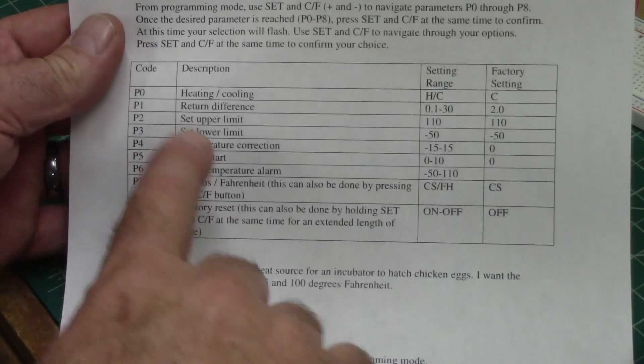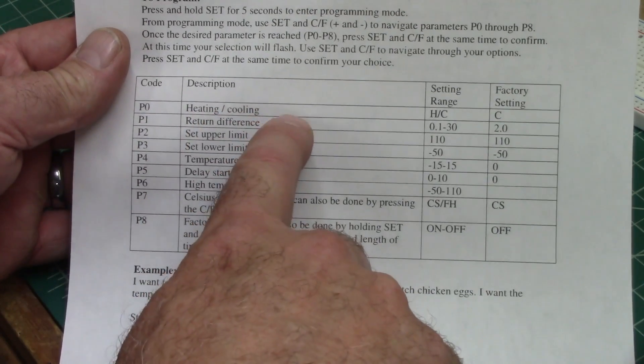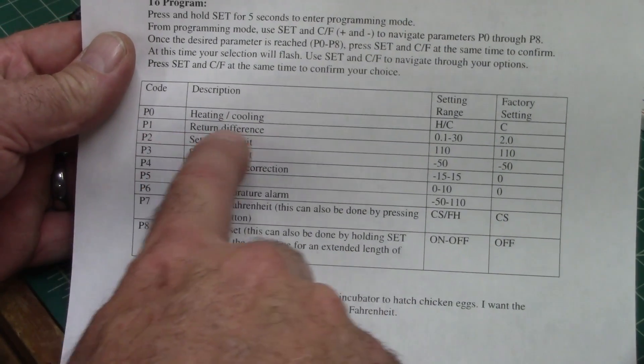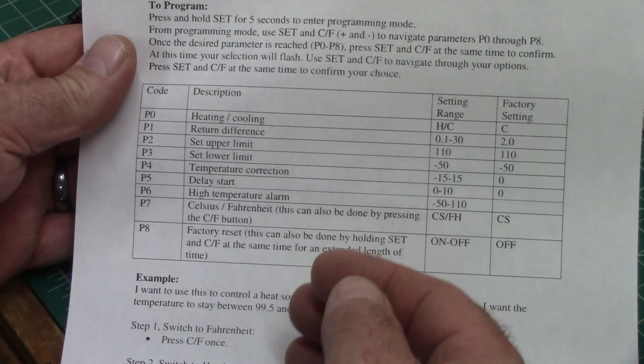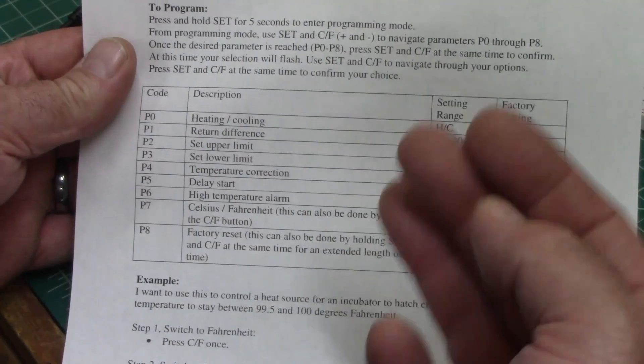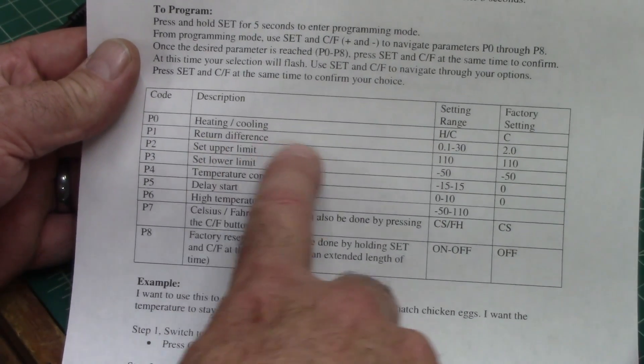So here's all the different modes. You got P0, heating and cooling, which we talked about. P1, return difference. That's the amount that it's going to vary before it's going to turn on and turn off. And we normally set that at two degrees.